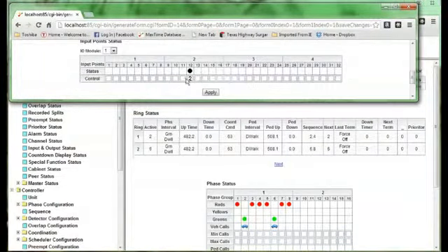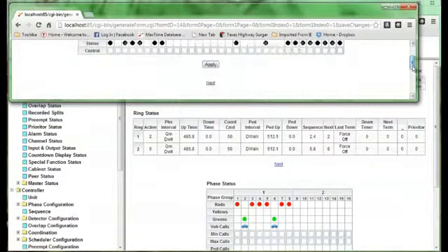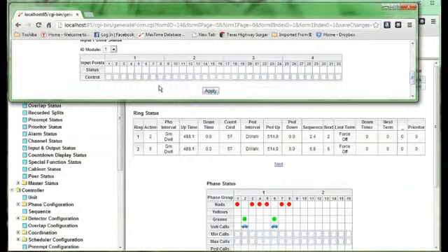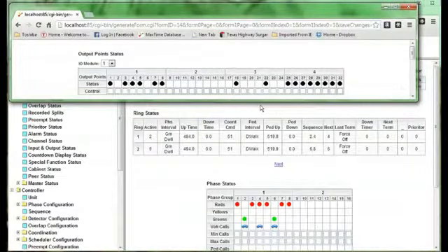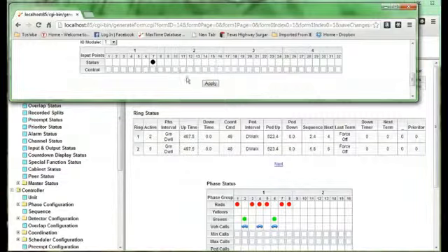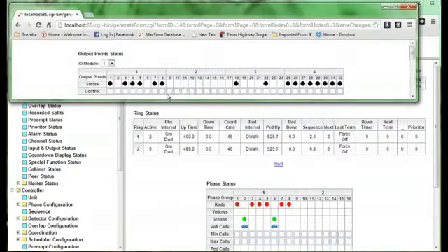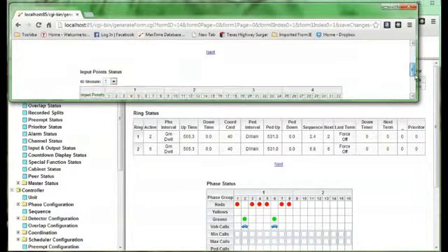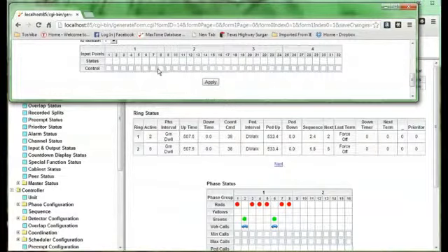So phase 4 is not going to come up unless the timer is running for the PED detector and phase 7 is true. So if he wandered out and he wandered back in, I put the vehicle call back in, and it will not be serviced because I'm running coordination. I got a big green band, so I have to wait until the timers come up and make it true.